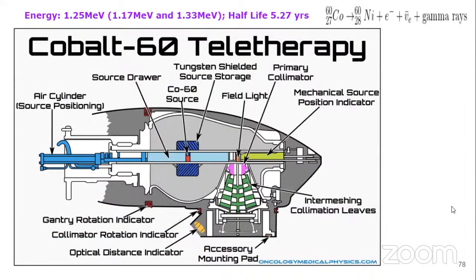So this is a cobalt 60 teletherapy machine. This is a basic thing. I'm showing this as a head, but even before it became an isocentric machine, there were different kinds of machines. In Tata Hospital, very early on, we had a Janus machine, two-headed. While you are setting up a patient in one room, the source goes to the other room and you're treating the patient in the other room. So it is just to economize time.